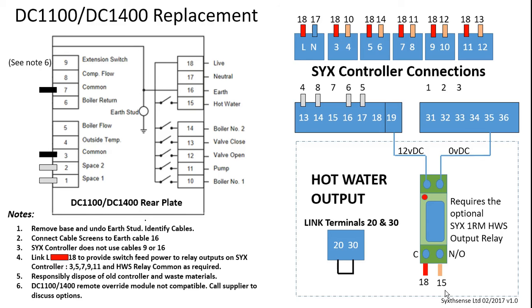Just a comment on sensors and options. If your existing arrangement does not have the sensor, then you do not need to connect it onto the SYX controller. However, we are trying to save energy with this product. If you can enhance the application by adding in sensors to improve the performance and the control of the equipment, specifically boilers, if we can maintain and control the boiler flow output to match the load of the system, then we will save energy. So if we can add a boiler flow sensor in and we can match the demands of the system, then we should take the opportunity to speak to the customer and see if they're prepared to enhance the system. The boiler return sensor on terminal 6 will provide plant frost protection.